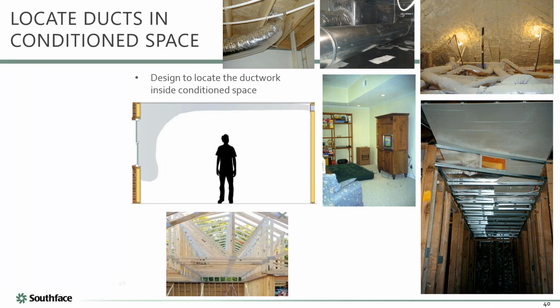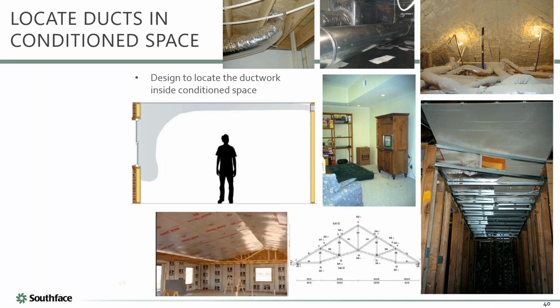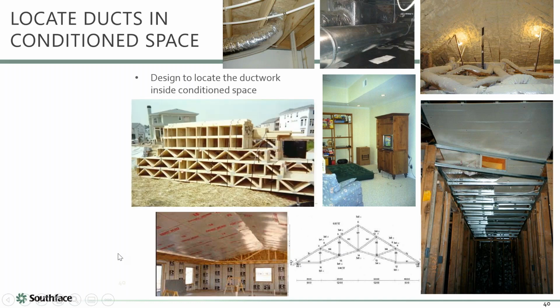It's, you know, a bump up is created, or it's kind of a form of a scissor truss. And this was a builder in Florida that was doing what they called a plenum truss, where they frame their house and not build the interior walls yet, set all the trusses, put a hard air barrier, and that creates this space where they can rough in all their ducts. They're going to put a finished flat ceiling in here, and then all the ceiling light fixtures and ductwork are in that interstitial space. And if you think about it, they have the same benefit of the spray foamed attic, only they used a much less expensive insulation here. So a pretty impressive design concept.